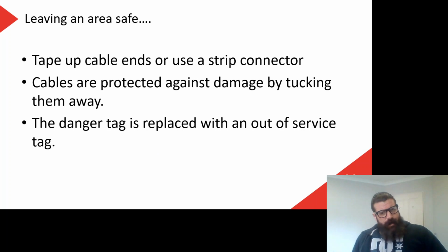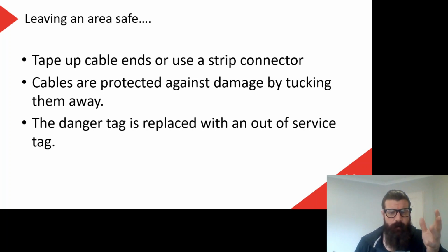So leaving an area safe. If we need to leave our isolation, we're finished for the day or going to do something else, but we're going to leave the isolation in there, so we haven't finished that work. There's a couple of things we need to do to make sure it remains safe. So we tape up the cable ends or use a strip connector, so any exposed copper in our cables is tidied up and no one can accidentally come in contact with that. It shouldn't matter if nobody switches it back on, but it's always better to be safe.